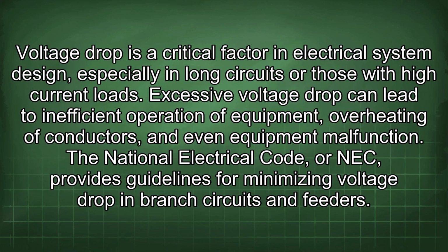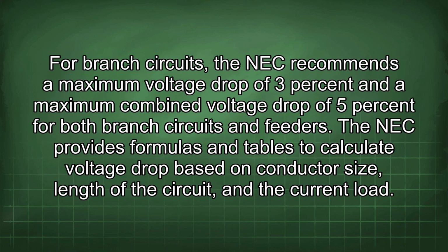Voltage drop is a critical factor in electrical system design, especially in long circuits or those with high current loads. Excessive voltage drop can lead to inefficient operation of equipment, overheating of conductors, and even equipment malfunction. The National Electrical Code, or NEC, provides guidelines for minimizing voltage drop in branch circuits and feeders. For branch circuits, the NEC recommends a maximum voltage drop of 3% and a maximum combined voltage drop of 5% for both branch circuits and feeders.